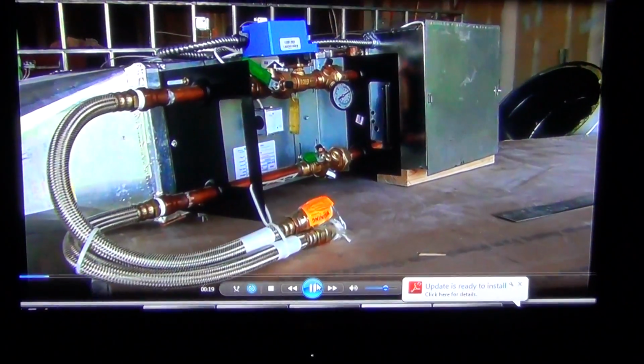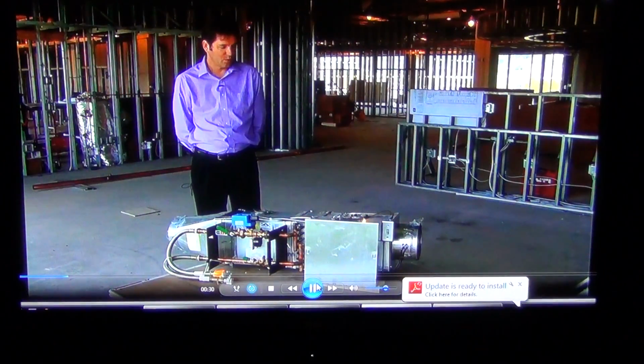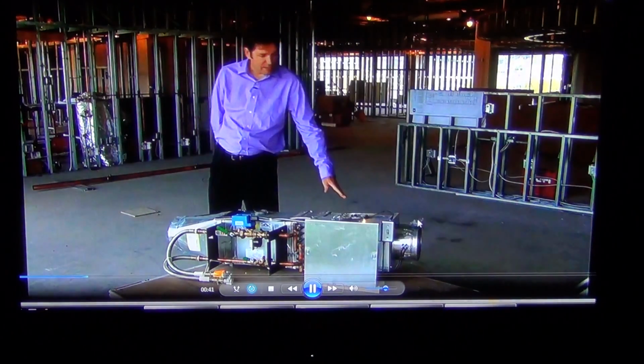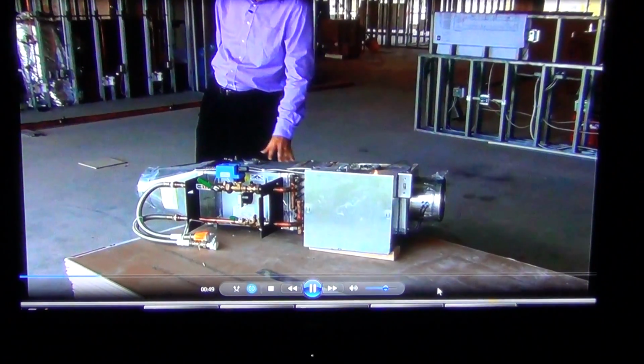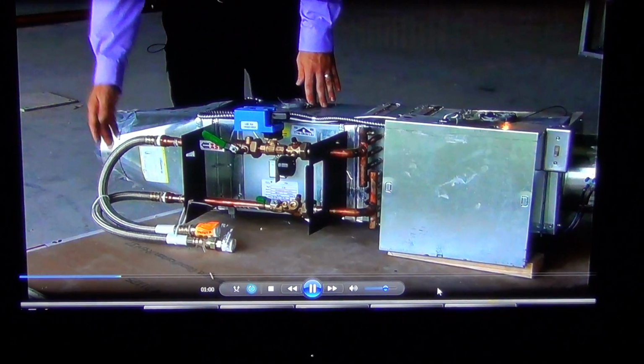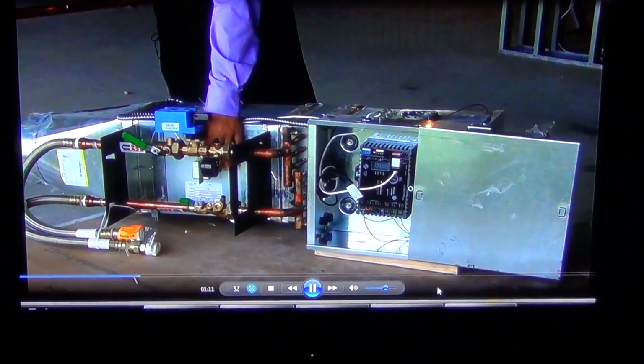Either available as a VRU by Johnson Controls, and VRU stands for VAV Ready Unit, or as a ZCU, a Zone Control Unit by Siemens. Normally what you would see show up on a job site is a significant amount of pieces of hardware as defined by the actual VAV box, control section, a square to round transfer unit, a control valve, an isolation valve package, a hose kit, a control box with the controller inside, as well as a discharge air temperature sensor.